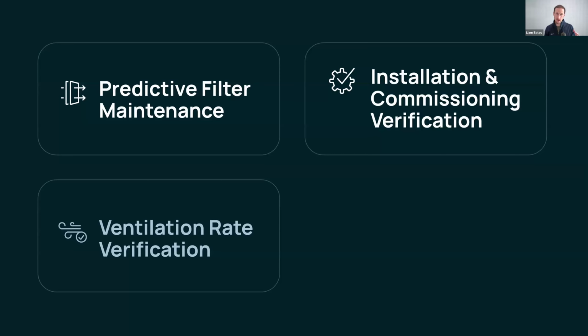Ventilation rate verification: now that we've got airspeed and we know the sizes of the ducts, we know exactly what volume of air is actually being delivered. There's a fantastic opportunity here around energy savings — not delivering more air than we need to, while still meeting code and delivering the correct amount of CFM per person.